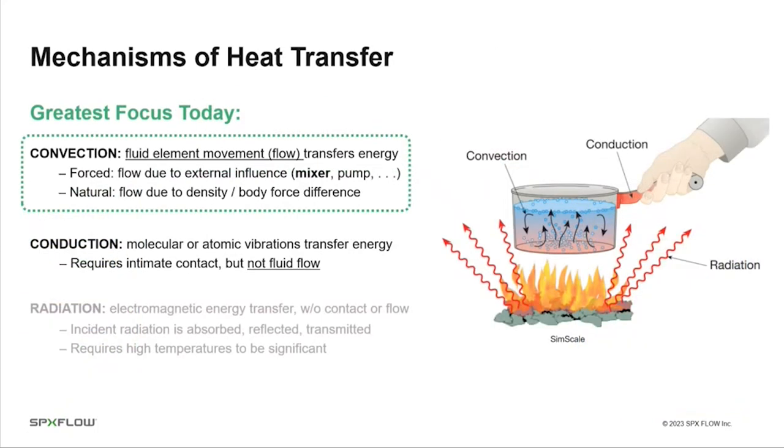This graphic shows three modes of heat transfer: convection, conduction, and radiation. In stirred tanks, it's the first two — convection and conduction — that are most important. Radiation is not important typically in a stirred tank because we don't have high temperatures, combustion, or flame sources. So how do we achieve and maximize heat transfer in stirred tanks? We do that by designing various heat transfer surfaces into our tanks and then optimizing their surface area and the flow across that surface area.